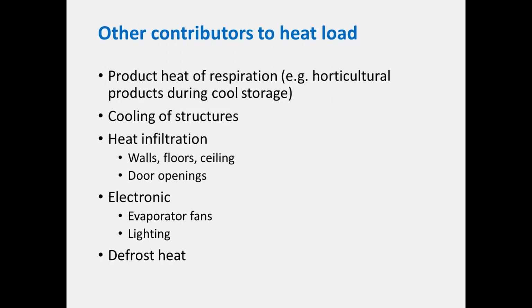So that's the load due to the product. You also need to recognize that in a refrigerated facility, whether a store or during temperature pull-down, some products will respire and give off heat of respiration, particularly horticultural products like apples and kiwi fruit. If you're entering product into a facility where the compressors haven't been running, so it might be at room temperature, you need to recognize that concrete and steel rails will also need cooling down, so add them to the calculation when starting from ambient temperature. Heat will also come in through the walls, floor and ceiling, which is why good insulation is needed to minimize that amount, and of course there's inevitable heat coming in through door openings, which we'll discuss more later. Another significant source of heat is the evaporator fans.